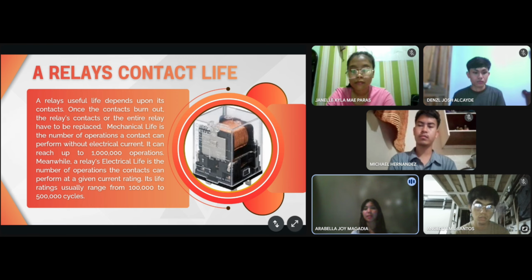So in short, mechanical life is how long it lasts without current, and electrical life is how long it lasts with current. And overall, the relay's contact life determines when it will need replacement. That's why, in real applications, we always consider both its mechanical and electrical life ratings to make sure the relay will be reliable over time.